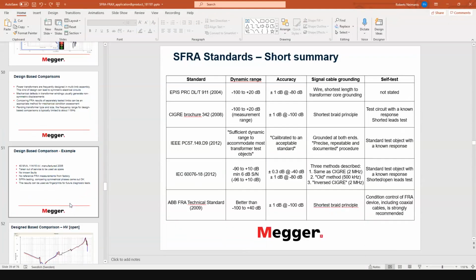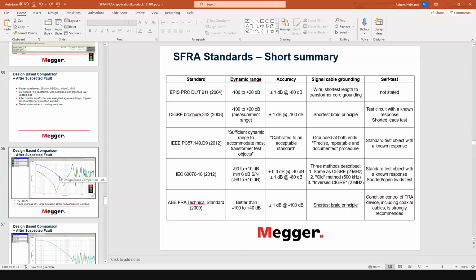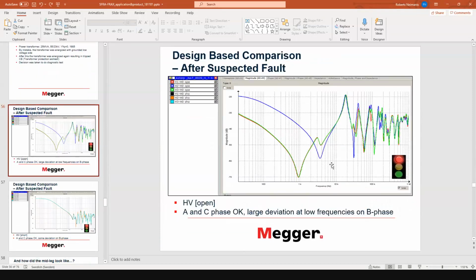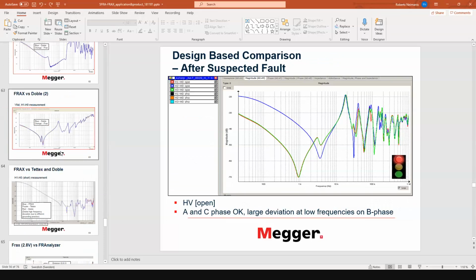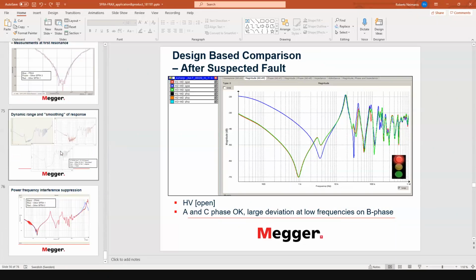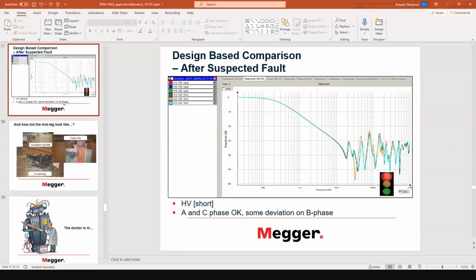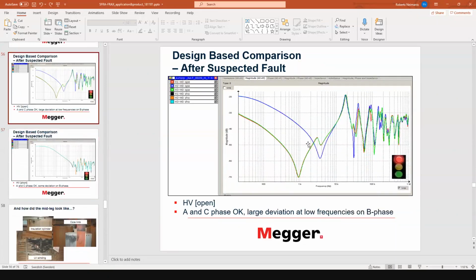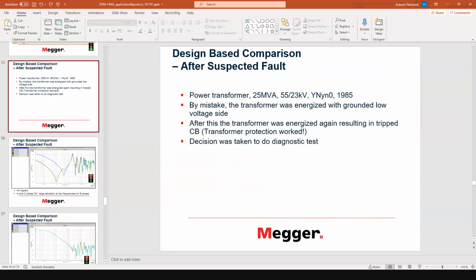Let's see. This is like a fault where you have a short-circuited winding. You see in one phase there is a very different response compared to the other two phases. I think, okay, I don't have in this presentation any good cases, but this is like a typical example when you have a short circuit in the winding. It was a power transformer which was energized and put into short circuit at the low side.